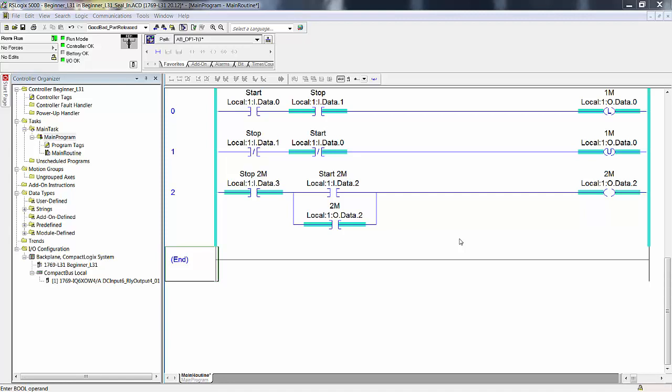Input 1 through 5, the normally open contacts on those push buttons are wired in parallel with the toggle switches. You can have a maintained on, maintained off, or normally open. So you just leave the toggle switch off, and then when you push the button, it momentarily goes on.